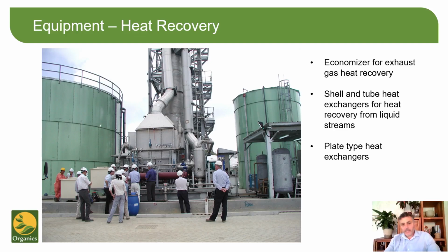For example, we have a cooling tower that transfers heat directly from the exiting wastewater into the incoming airstream. We also have a plate heat exchanger that recovers heat from the exiting wastewater, putting it into the incoming wastewater too. The incoming wastewater is further heated with a condenser that takes heat from the exiting airstream prior to being introduced to the thermal destructor. This both reuses the heat, but also reduces the thermal load on the thermal destructor by reducing the amount of moisture being carried in the ammonia-laden air that will be taken as combustion air. Using recovered heat improves the energy efficiency of the system, but extends the startup time. So a good understanding of the customer's priorities is important.